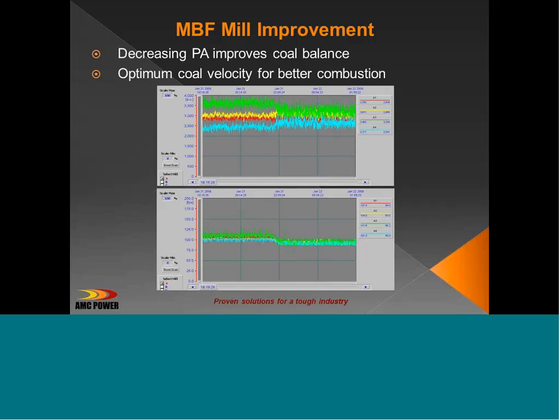And this particular screen I like to show because it shows the importance of both mass flow measurement and velocity measurement. The top screen is the mass flow of 4 burners out of an MBF pulverizer. And you can see the distribution from the green pipe down to the blue pipe. On the lower screen, we're looking at the speed of the particles as they move through the coal conduit. And you can see these are over 100 feet per second.